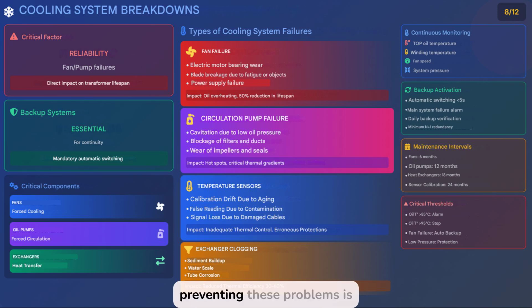The key to preventing these problems is continuous monitoring via SCADA, which records variables such as oil and winding temperatures, fan speed, and system pressure in real time. This information allows for predictive maintenance and prevents major failures. Furthermore, backup systems must be activated in less than 5 seconds and checked daily with a minimum architecture of 1+1. Strict adherence to maintenance intervals: 6 months for fans, 12 months for pumps, 18 months for heat exchangers, 24 months for sensors, is vital to avoid surprises.